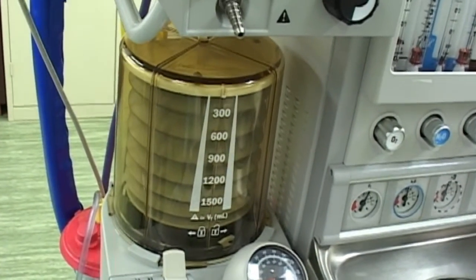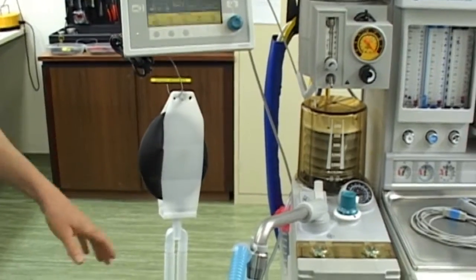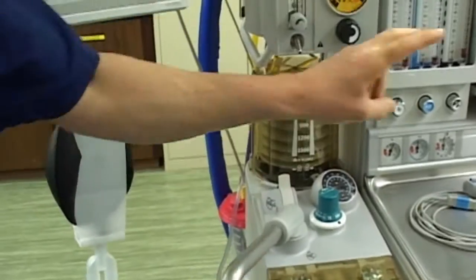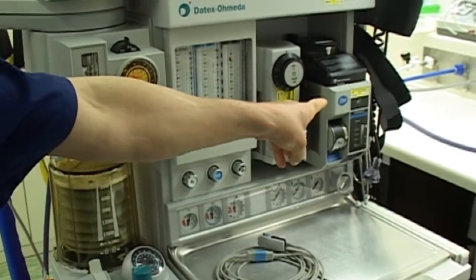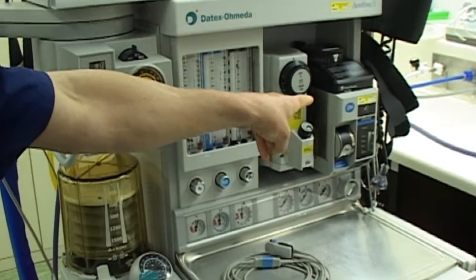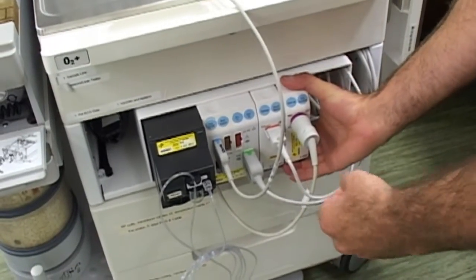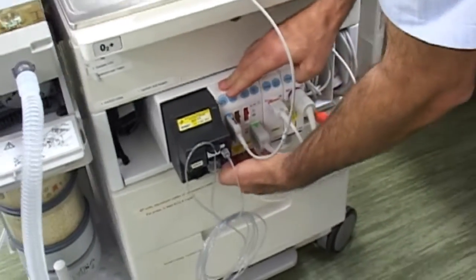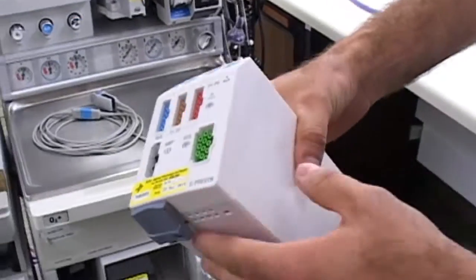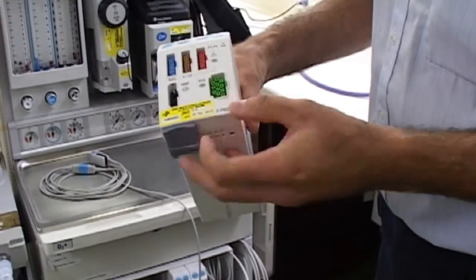I have an opportunity now to look at the gas side of this which is the ventilator here and we've also got two anaesthetic agent delivery units there. These are all modular devices. What we'll do is we'll just take a module out. This module, when it's hooked into this rack, will actually measure all your vital signs.